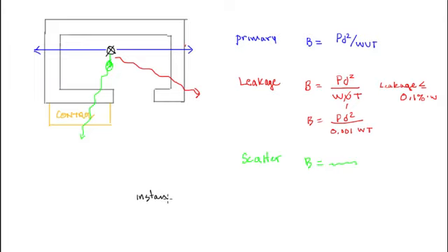And then a final important requirement for all shielding calculations has to do with the instantaneous dose rate that comes out. And the regulations here say that the dose rate has to be less than 2 millirem in any 1 hour. And that's often the limit that you run into when you do shielding calculations.